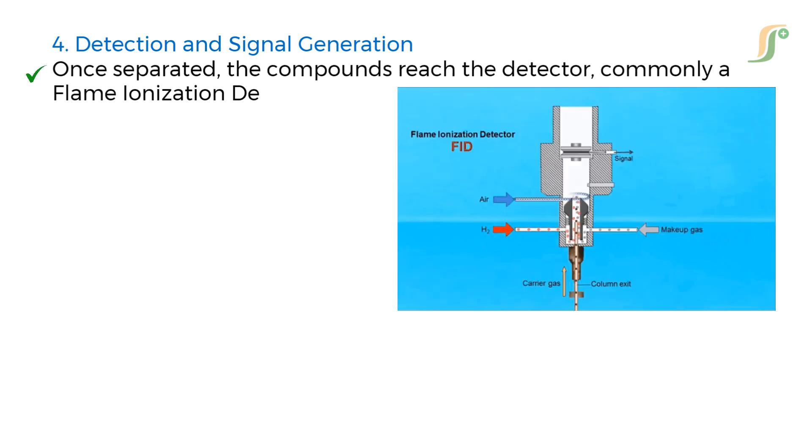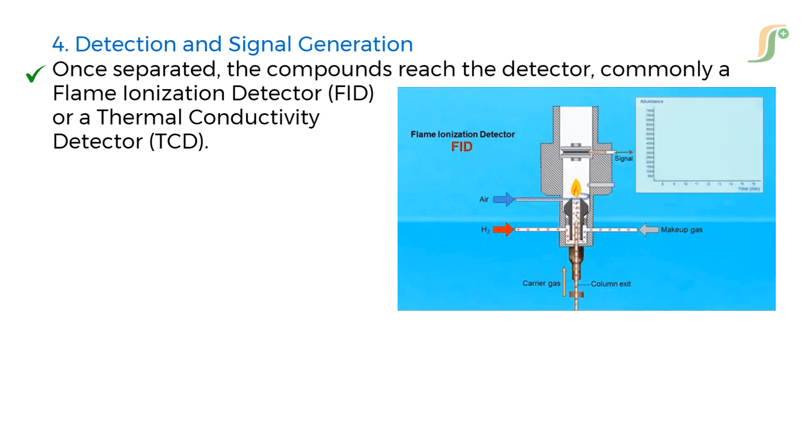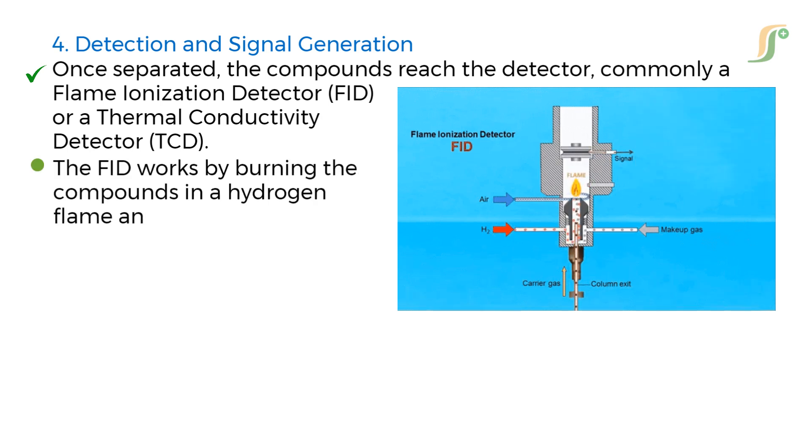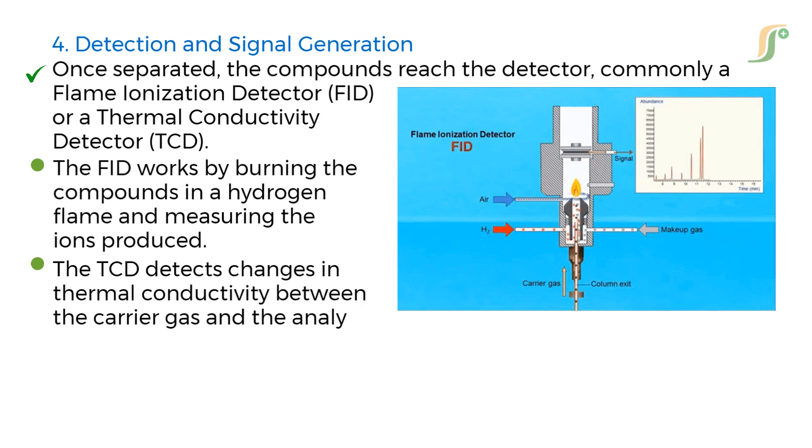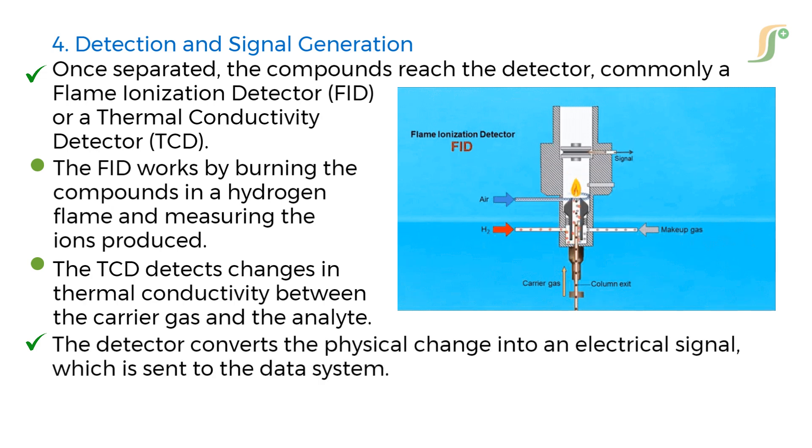Fourth step is detection and signal generation. Once separated, the compounds reach the detector, commonly a flame ionization detector, i.e. FID, or a thermal conductivity detector, i.e. TCD. The FID works by burning the compounds in a hydrogen flame and measuring the ions produced. The TCD detects changes in thermal conductivity between the carrier gas and the analyte. The detector converts the physical change into an electrical signal, which is sent to the data system.